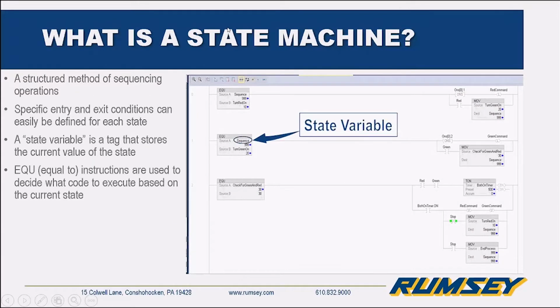So what is a state machine? Now, granted, that first statement can be said about almost any program as a structured method of sequencing operations. Specifically, the big idea is it's centered around the equal to statement and the move statement. So equal to being the entrance, what to code, what to execute, and if it's in the correct state, and then the move being the way to get out of the state to the next state. What they're looking at is a single variable, typically a double integer in Logix 5000, we'll say, but typically an integer value that is read from and written to chug the program along from state to state with input conditions and output conditions.